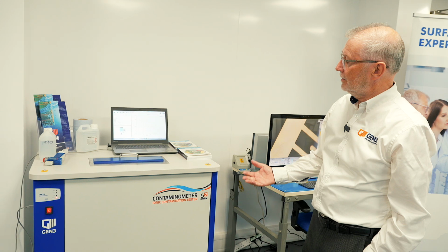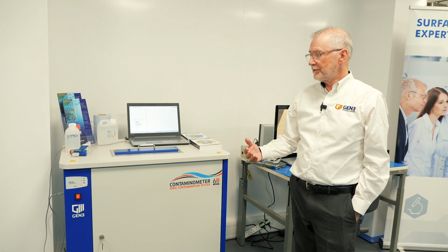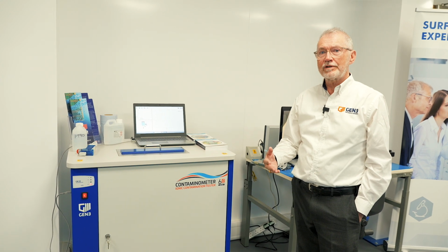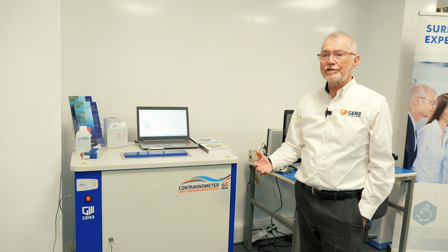We have the Gen 3 contaminometer, so that measures ionic impurities or surface residues that are left on a circuit board following the manufacturing process. This machine is very good at capturing any of those residues, those ionic residues.